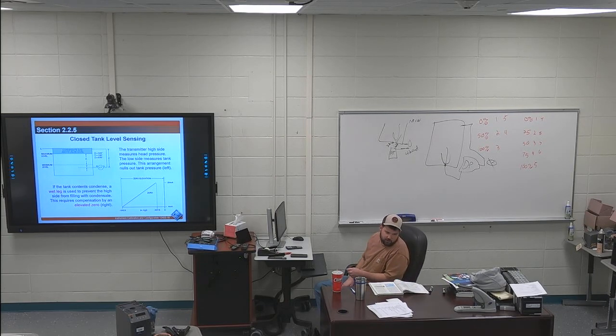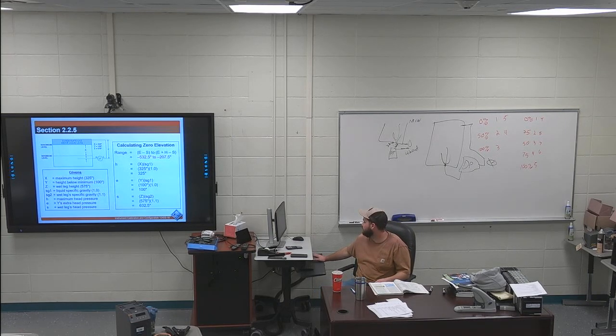226, Rosemount zero and span. Brandon, this should look fairly familiar to you. With the plate. Got the little plate that you swing that's always out of the way. You will do a zero and span calibration on that 5552 trainer. But they go through the steps on that and how you swing the plate out. Then there's two little buttons. And because they put ours so close to the thing, you've got to take like an Allen wrench to push it all the way down.